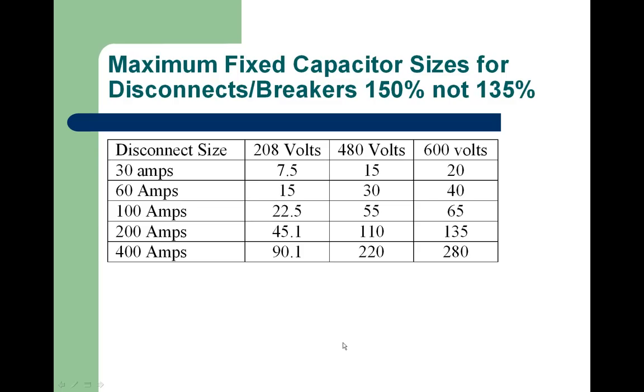This next slide again shows you what size capacitors you can put on breakers or disconnects. Typically in the electrical code, both for Canada and the U.S., they are sized at 135%. We have found that if you size the disconnects and the wire for 135%, fixed capacitors in particular are on all the time, and they get quite warm. We typically recommend 150% for the disconnect, the breakers, as well as the wire size.